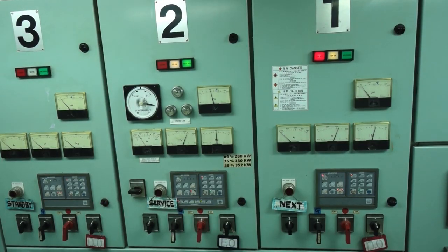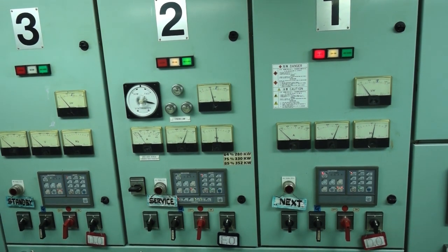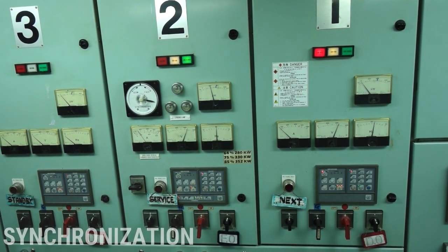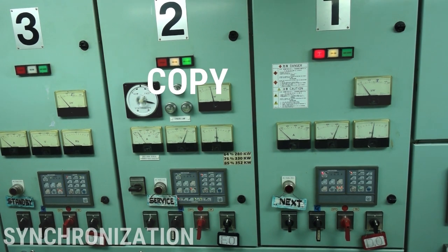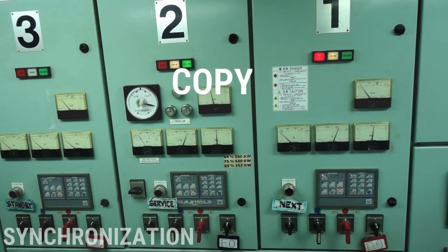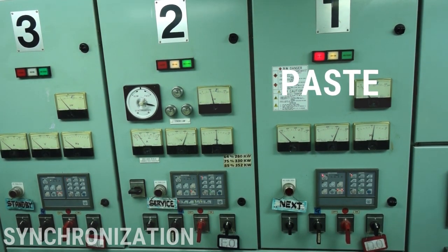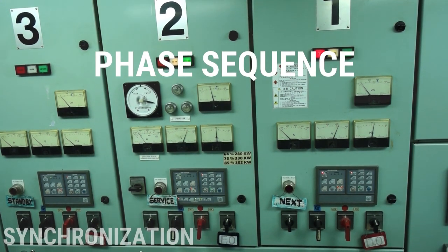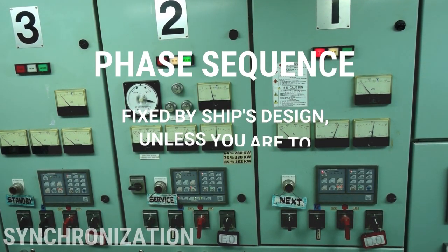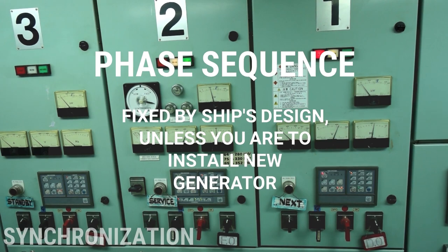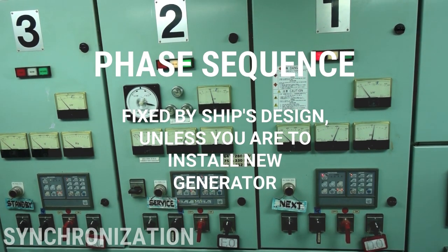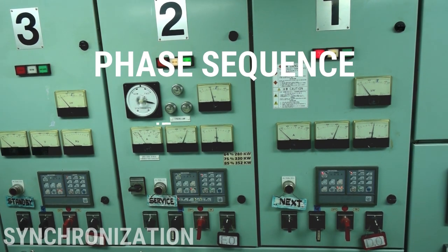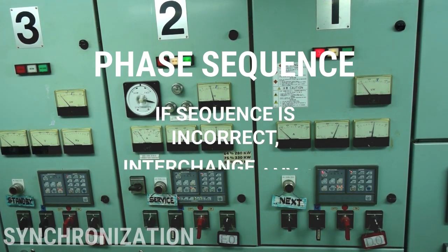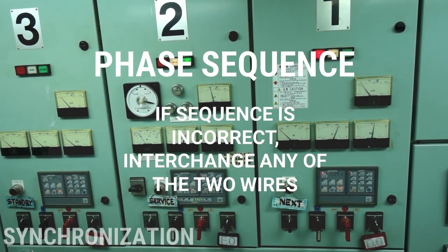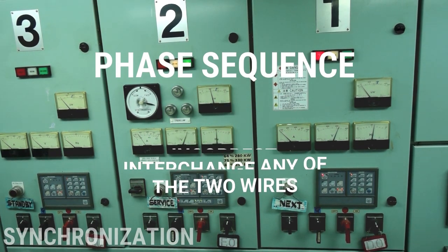Now that the incoming generator engine is running, the second step is synchronization. It means to copy the running generator's parameters to the incoming generator. For phase sequence, generators are already installed by the ship's plan. Often we don't really need to manipulate the order of it. Unless you are to install a new generator to the system, then you need to have a phase sequence indicator and check whether the phase sequence is in correct order.